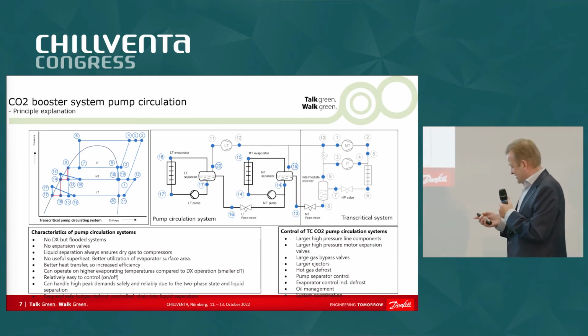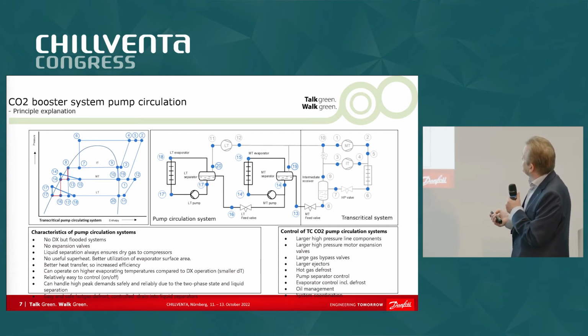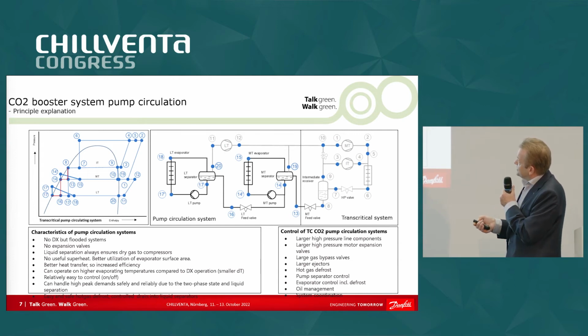Okay, this is a busy slide. This is how, how to explain, how does a flooded system work? So here we have the transcritical cycle. We have, for instance, the high pressure receiver, the medium temperature compressor, the parallel compressors, and the low temperature compressor. So what happens? We have liquid, CO2 liquid. We expand it into the medium temperature separator. That's this line. And then again, we expand it again to the low temperature separator. And that's this line. The pumps pump it around like this and like this. That's this cycle here and this cycle here. And that basically describes in a nutshell what happens.